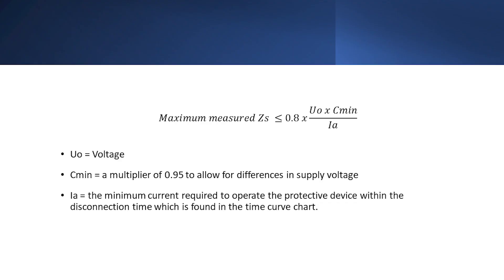Appendix 3 also explains that the maximum measured ZS must be less than or equal to 0.8 multiplied by that same calculation — in other words, 0.8 multiplied by the values in table 41. This is due to the operating temperature of the cable when it is under load.